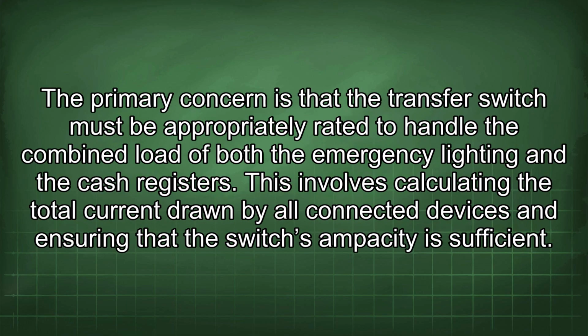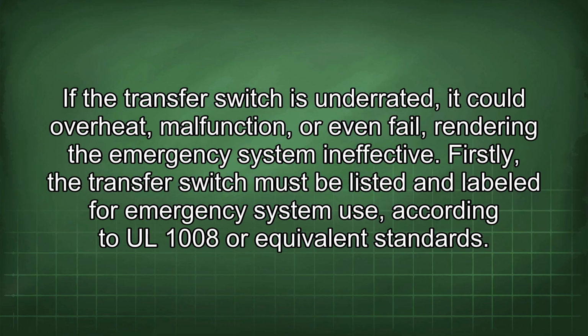The primary concern is that the transfer switch must be appropriately rated to handle the combined load of both the emergency lighting and the cash registers. This involves calculating the total current drawn by all connected devices and ensuring that the switch's ampacity is sufficient. If the transfer switch is underrated, it could overheat, malfunction, or even fail, rendering the emergency system ineffective.